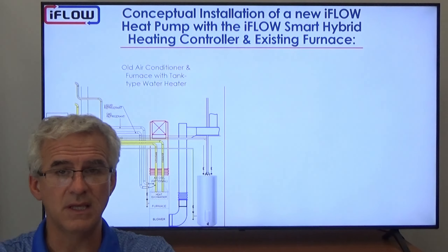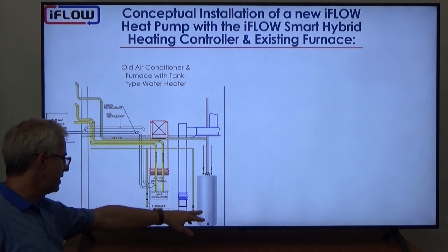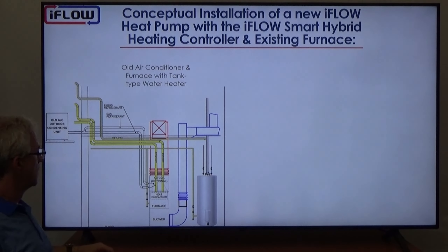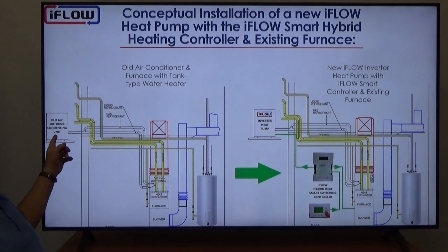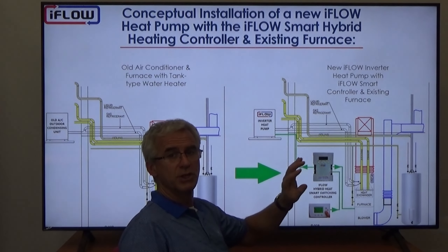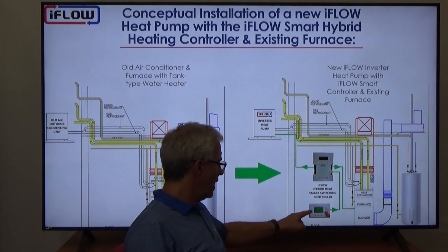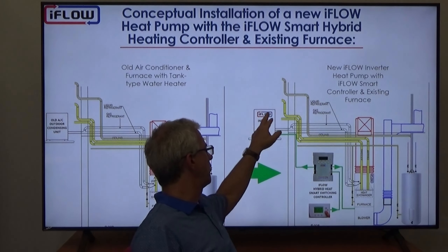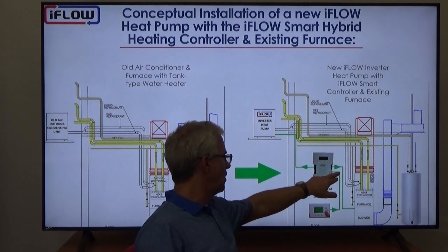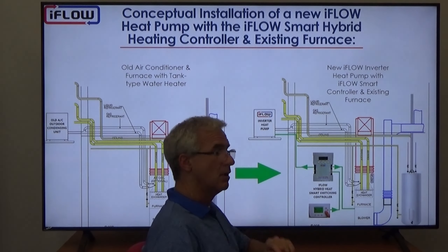Looking at the equipment: on one side we have the old outside air conditioning unit, a tank-type water heater, and a typical furnace with ducting. What we're going to do is switch out that old AC unit for an iFLOW inverter heat pump. We install the iFLOW switching controller so that we can input the parameters for automatic switching — no need for the homeowner to manually switch from electricity to gas. We wire the thermostat into the switching controller, then wire the output to the heat pump and to the furnace.